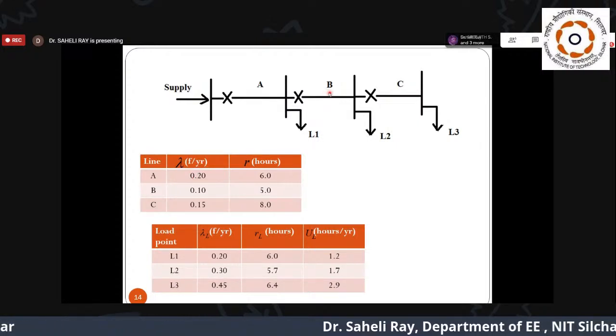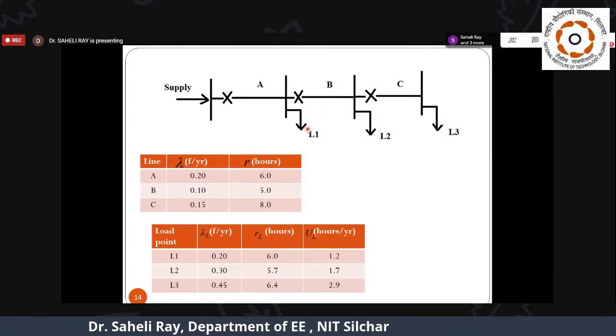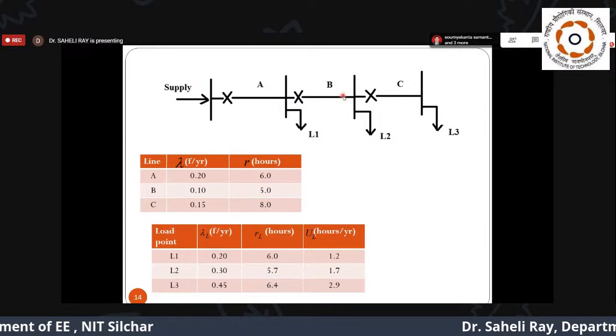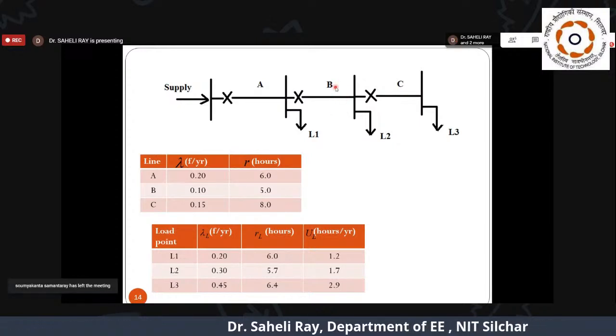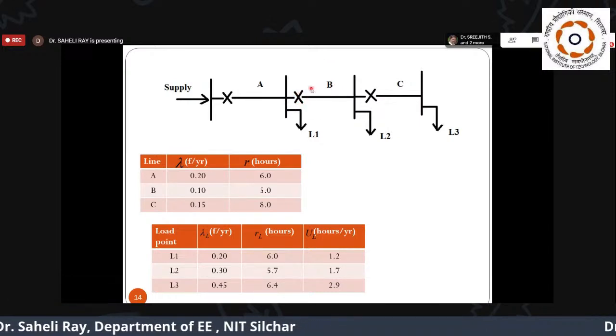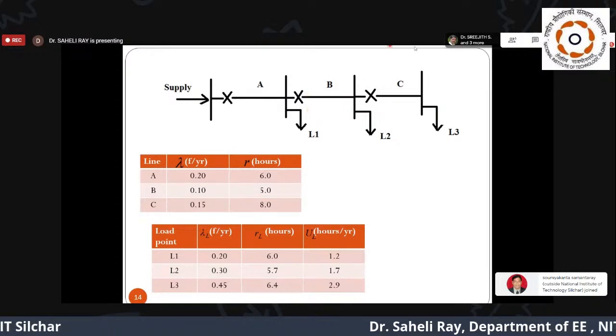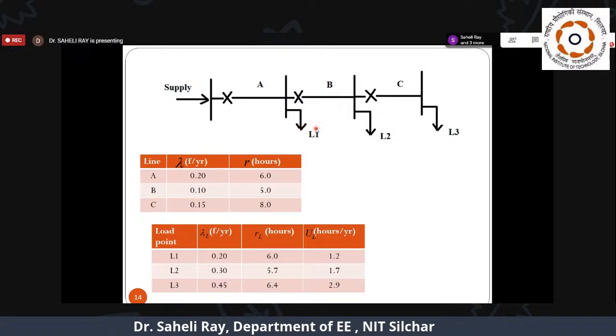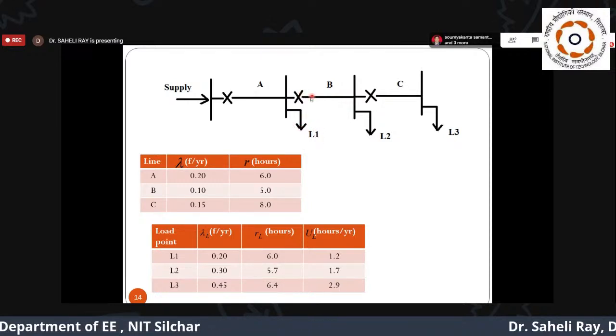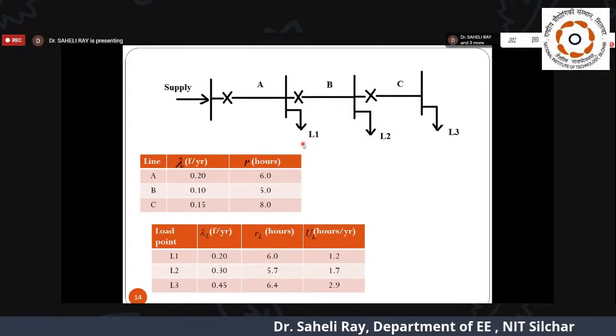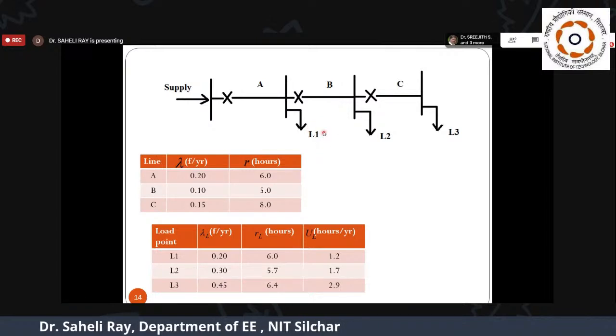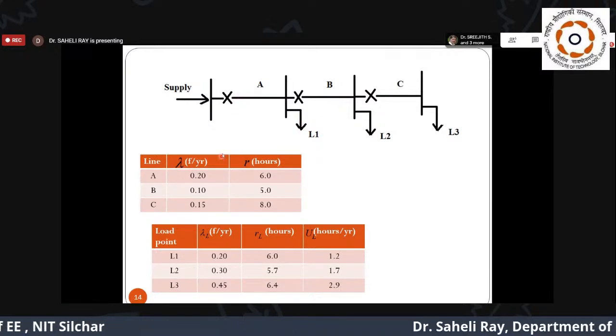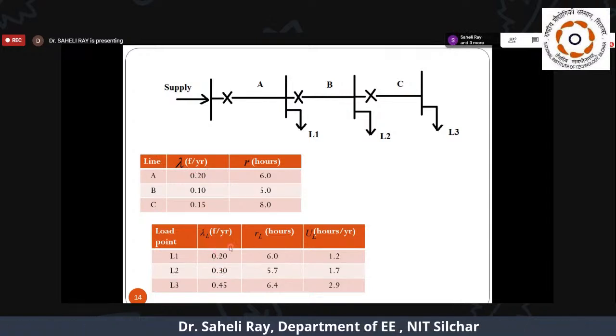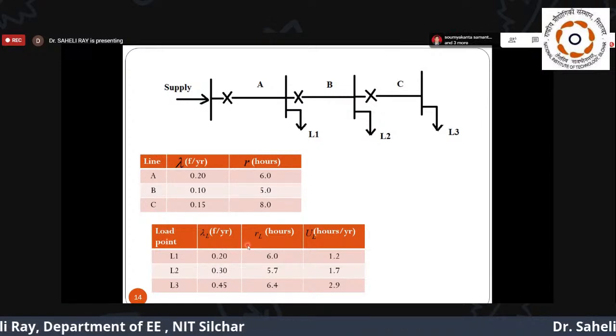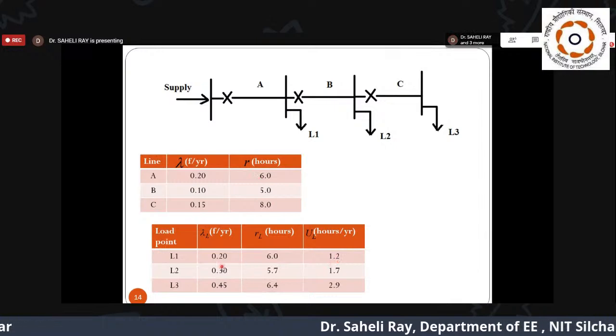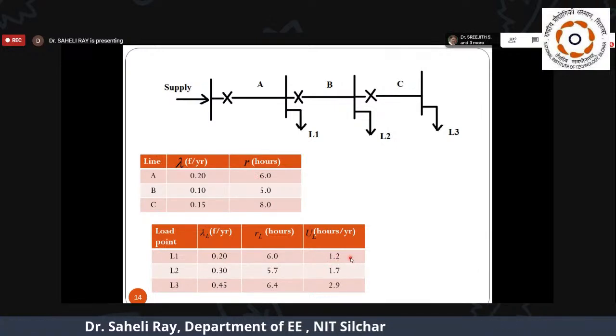Now suppose in the next case a fault occurs in this segment. Will it affect load point L1? It will not, because if a fault occurs at B, this circuit breaker will operate and the faulty portion will be isolated from this portion. As a result, L1 will not be affected. Similarly, if a fault occurs at C, there will be no effect on L1. As a result, the failure rate of L1 will simply be the failure rate of segment A. That's why we have just written 0.2 here. And the repair time is 6.0. Multiplied, 6 into 0.2 gives an annual outage duration of 1.2.